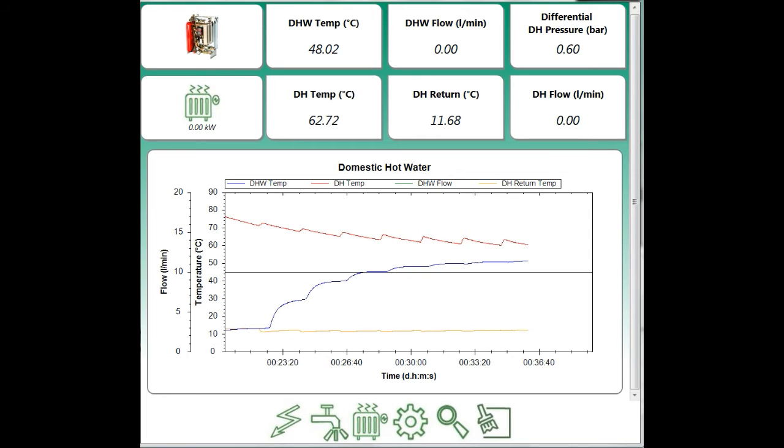Now, this is ten minutes later. You can see how there's been a few pulses now. And the domestic hot water temperature has crept up above the target. The district heating flow temperature has also dropped. But we can see the pulses clearly.